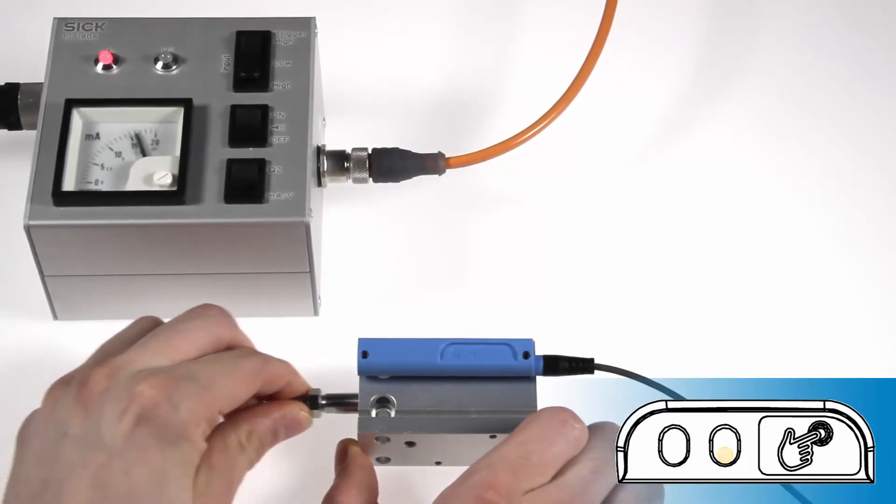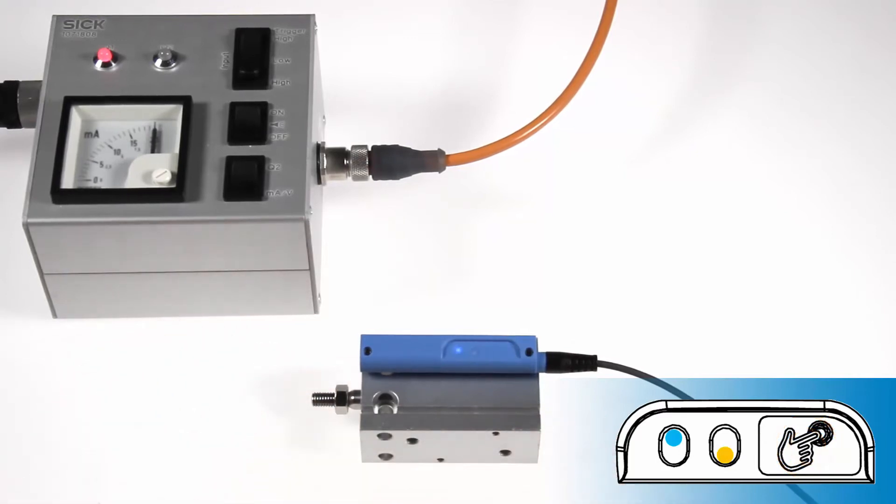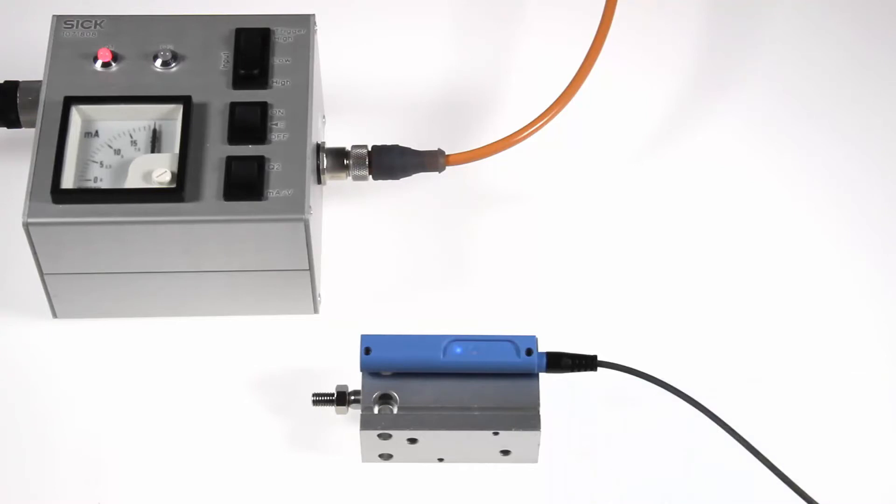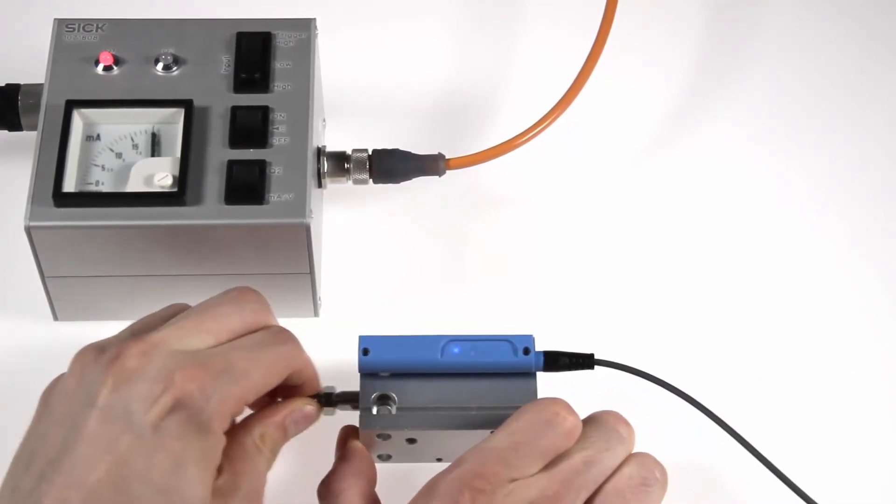Now push the piston to the end of the measuring range and press the keypad once again. The yellow LED stops flashing and the end of the measuring range is set. The analog output now gives a 4 to 20 mA signal in the set range.